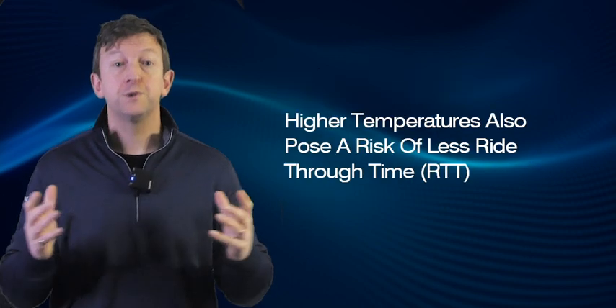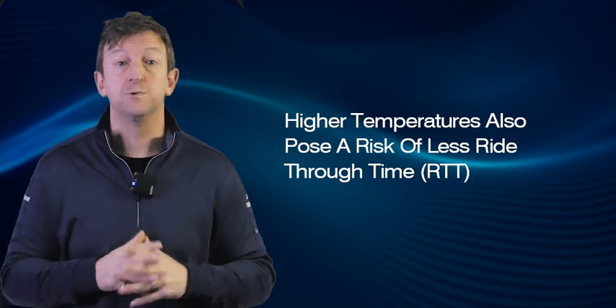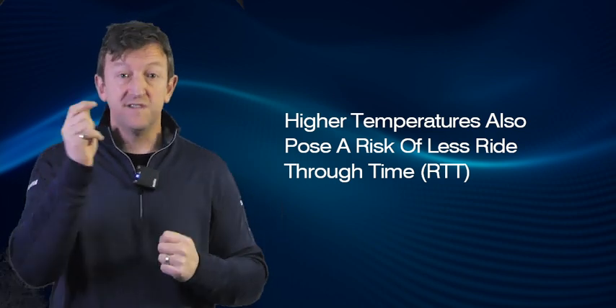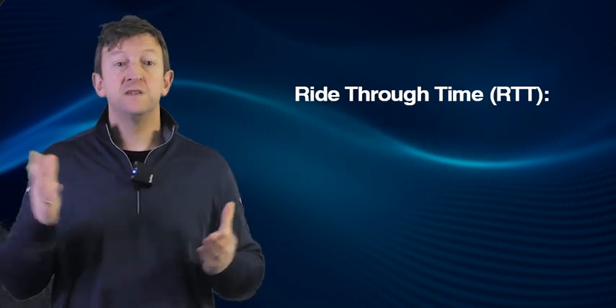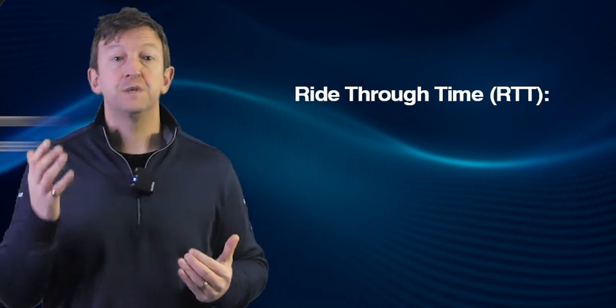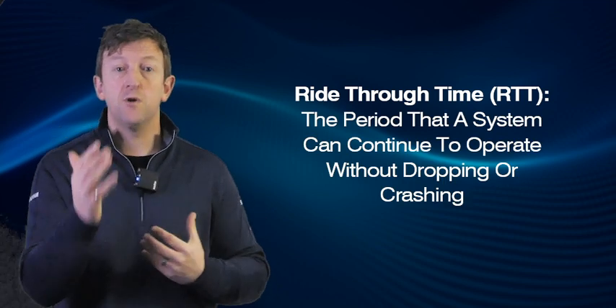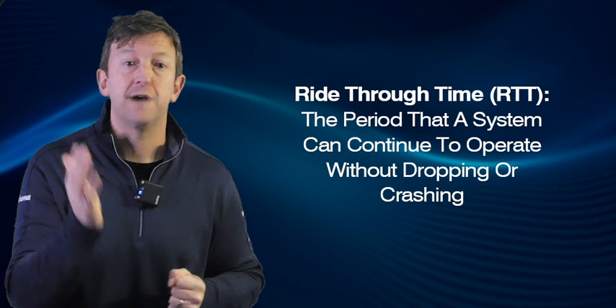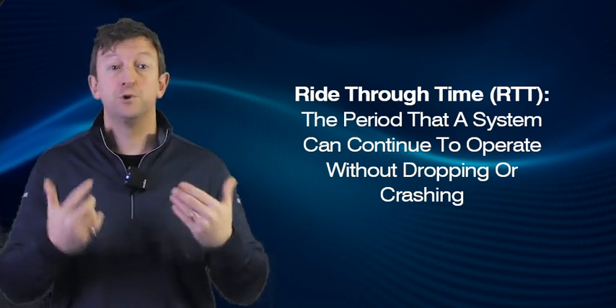Higher temperatures also pose a risk of less ride-through time, which is a larger risk if you lose cooling. Regarding the definition of ride-through, this is the period that a system can continue to operate, typically during a loss of power or a short-lived event, without dropping the system.